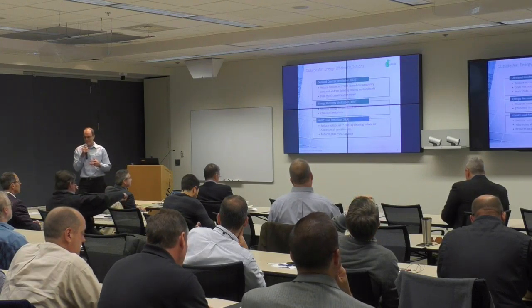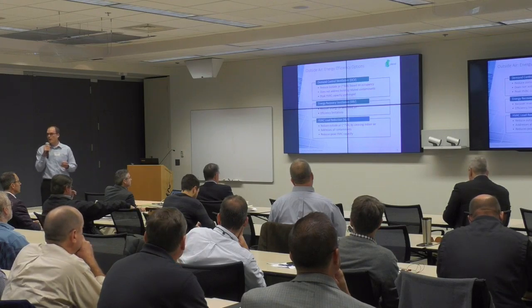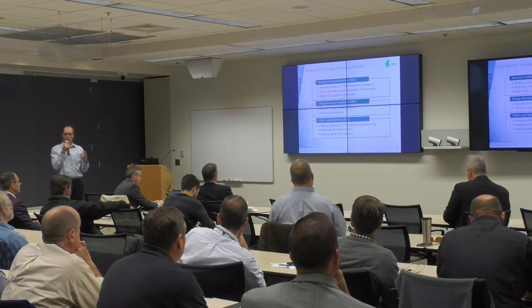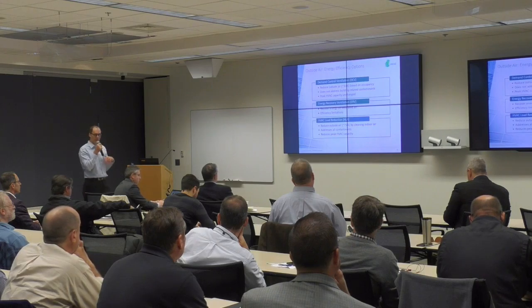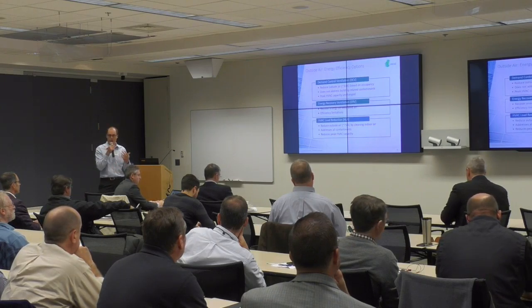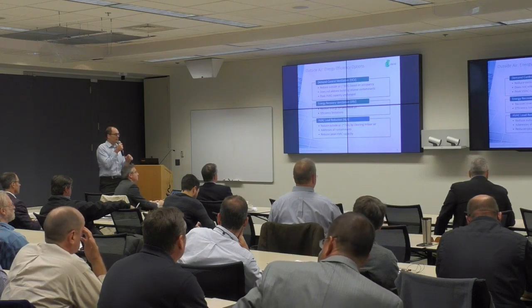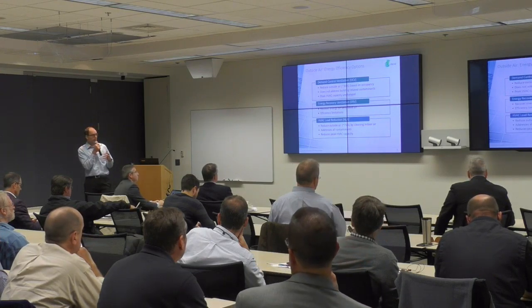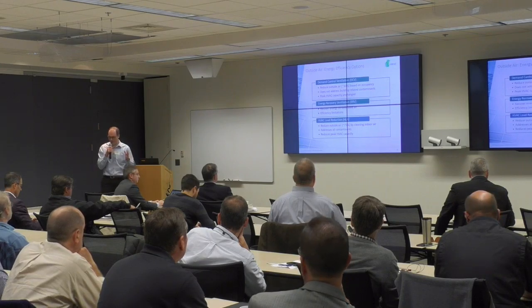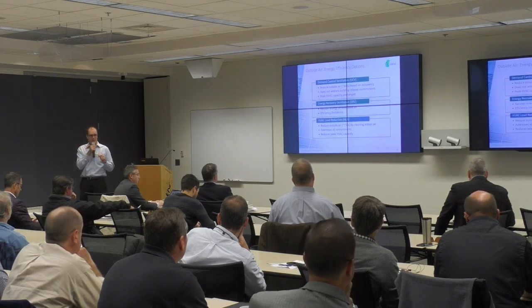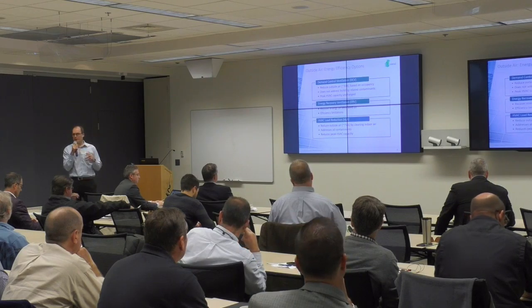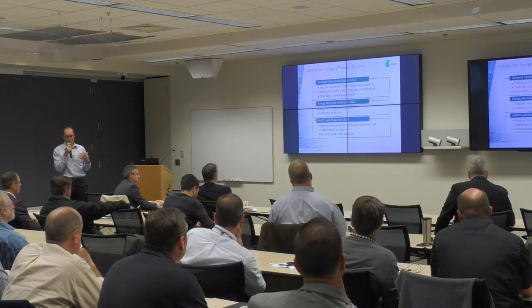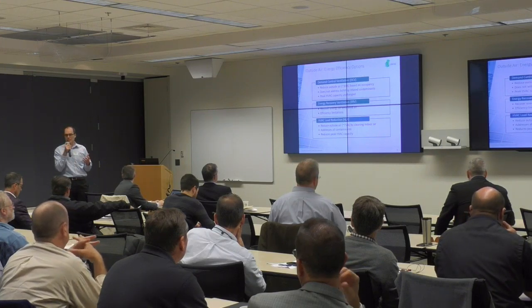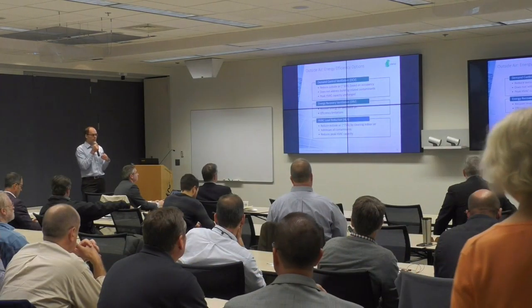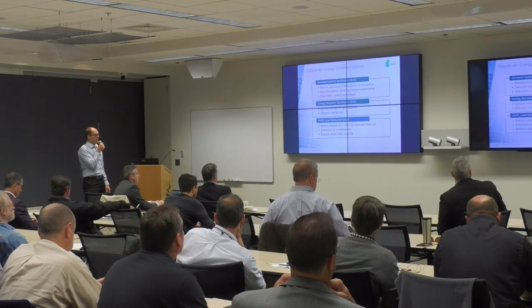So some of the common things you see would be demand control ventilation, where you reduce ventilation based on lower occupancy in the building. With lower occupants you have lower CO2, so you don't necessarily need as much ventilation. But it doesn't address the building contaminants, so you still need a fair amount of ventilation for that. The other aspect is you don't change the peak HVAC capacity, so on a hot afternoon at peak temperature, which is also typically peak occupancy in an office building, you still have to fully ventilate the building.